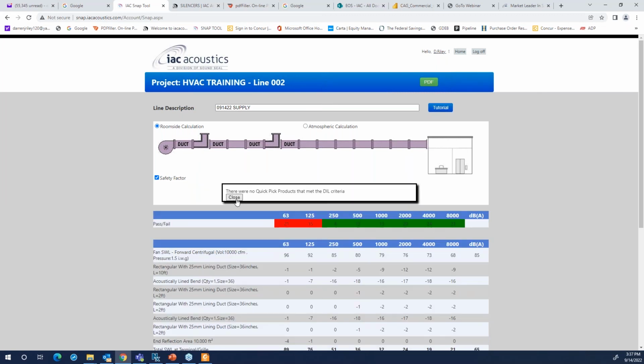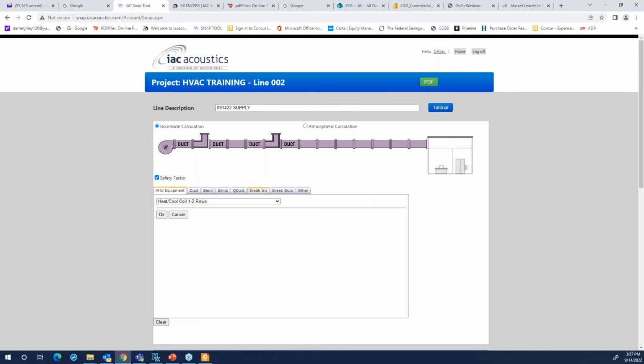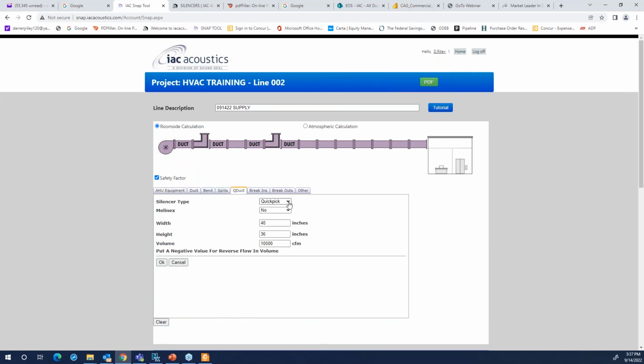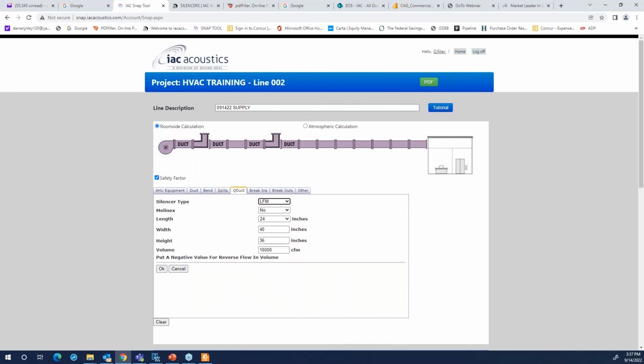So what I like to choose, and this is my silencer of choice, is the LFM. It is a good starting silencer when selecting a silencer. It is low frequency mid-grade, meaning it's going to give you really good mid-grade octave insertion loss numbers from the 125 to the 1K mid-range, at the same time keeping low pressure drop.